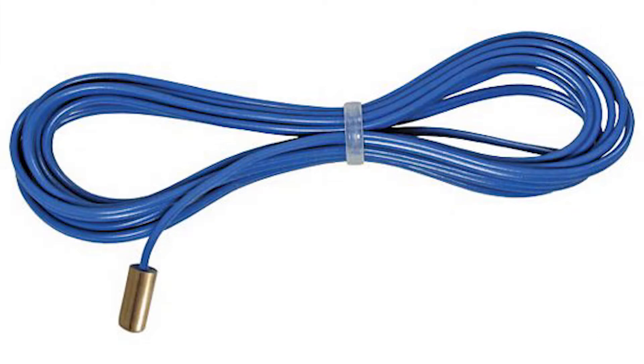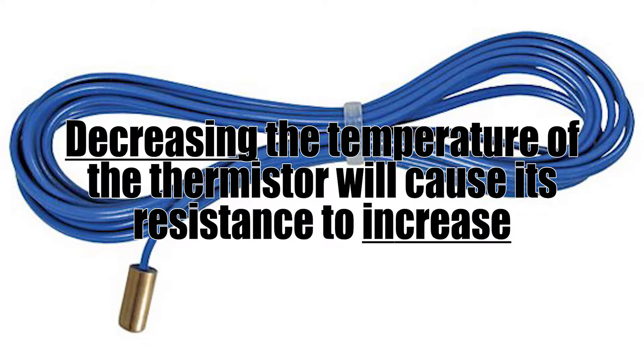Now the thermistor is a device that we use in the heating trade that does just that, except opposite. It's a temperature measuring device that when it gets warmer its resistance goes down, and when it gets cooler its resistance goes up — just flipped right on its head from a copper wire.